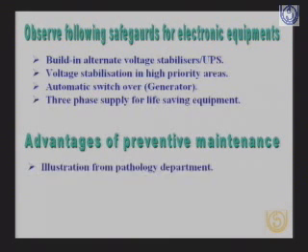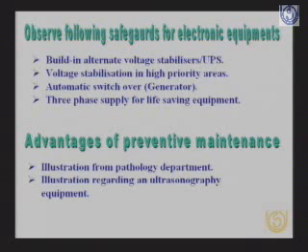And most of these equipments are high cost, sophisticated. So we should go for, especially for the equipments in the intensive care unit, OT, etc., that area should have voltage stabilization, or we should have uninterrupted power supply systems, like we get the UPS with the computers these days, which we have in our offices.